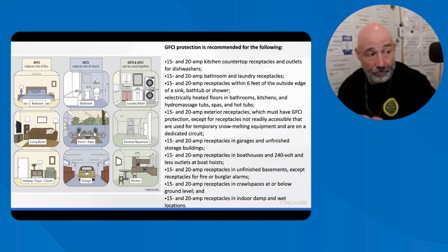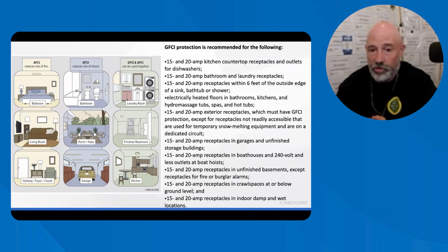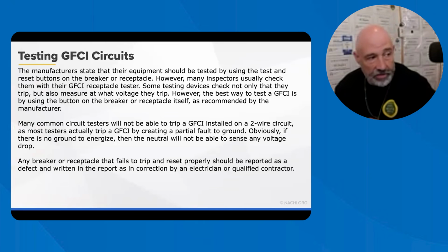Sometimes you'll find both AFCIs and GFCIs, like in bathrooms, and it gets a little complicated. Screenshot this so you know what you're looking at. GFCIs should be in places like finished basements, kitchens, boathouses, and damp locations. Any damp location should have GFCIs. Testing the GFCIs, I do recommend that you press the button. If you have testers, go ahead and test with the tester button. That should help you most of the time.